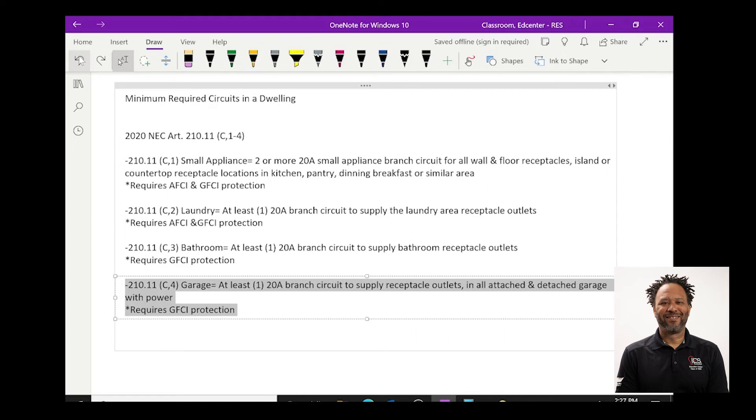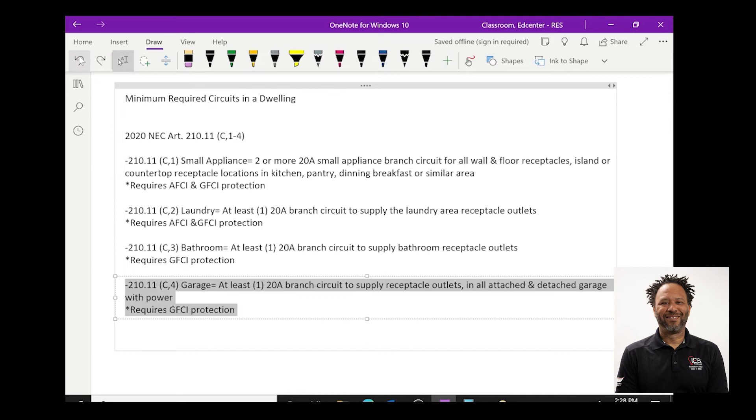So, that being said, if you have a detached garage that has no power to it at all, you are not required to run a 20 amp circuit to it. However, once you decide to put any sort of power to that garage, the requirement is that it has to be at least one 20 amp branch circuit to supply that garage.